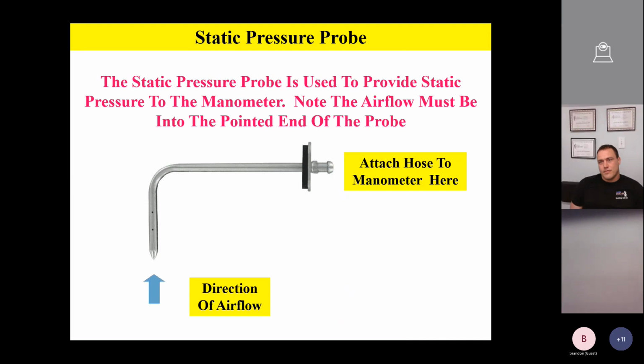So the static pressure probe, as you can see, is used to provide static pressure to the digital manometer. Now, please note the airflow must be into the pointy end of the probe. And I like to always stress this because we want to make sure that we position this probe. You'll notice this probe is bent 90 degrees. And by the way, they come in different lengths.